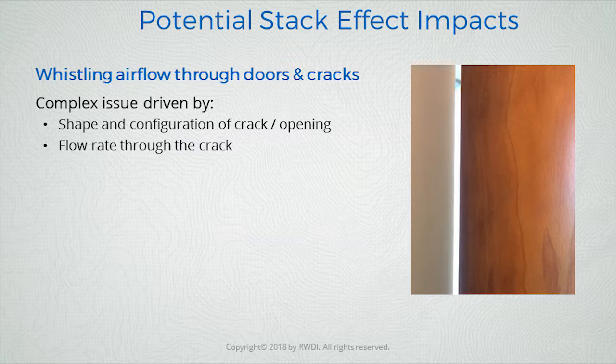The flow rate through the crack can set the tone, and that sound can range from something like a whistle to a hum. And I've even recently in a building tour heard of a flapping noise where a piece of rubber was flapping backwards and forwards and creating a rather unusual sound. So that kind of auditory noise can either be something that's benign or it can be a problem. And in some cases, the whistling noises in an apartment building can actually cause problems for people to sleep.